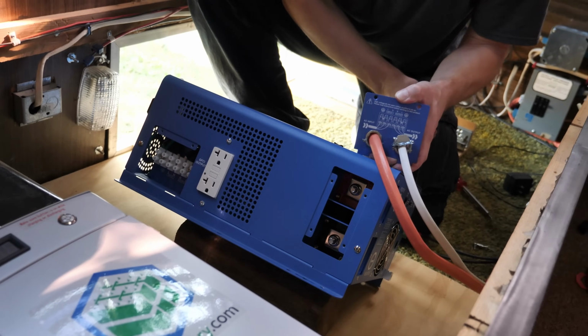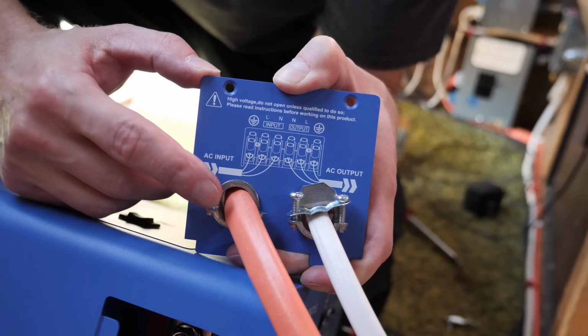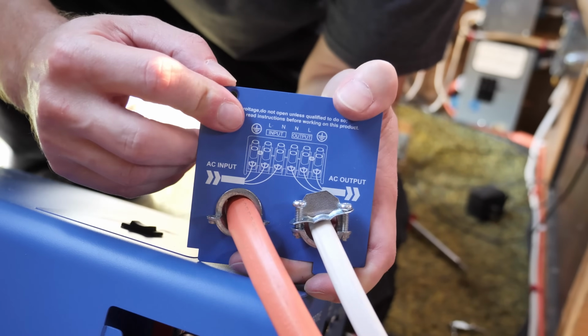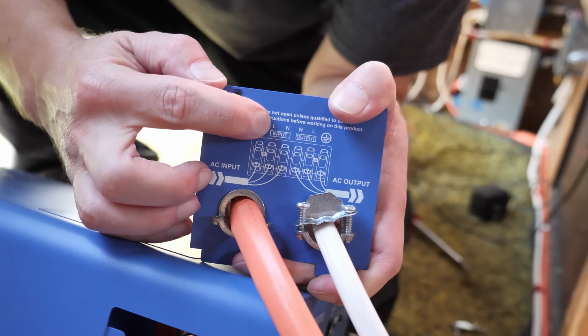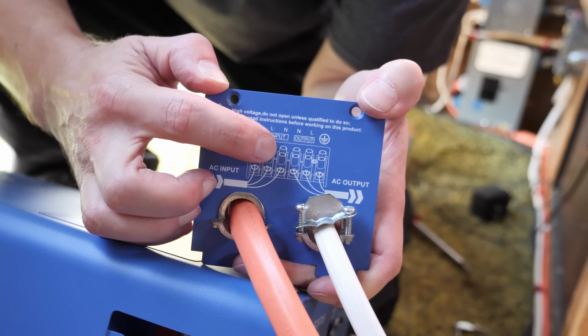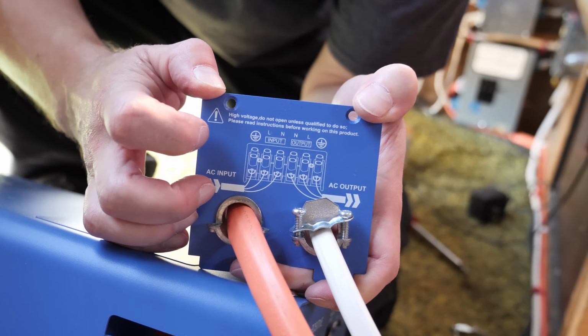If you look right on here, there's a wiring diagram, but your AC input is this 10 gauge wire. First thing we're going to do is hook up the ground, then line, which will be black, and then neutral. Then the same thing for the 12 gauge, which is the AC output.